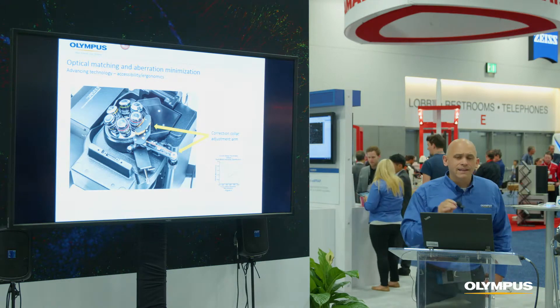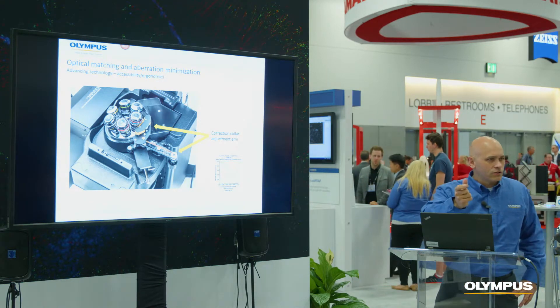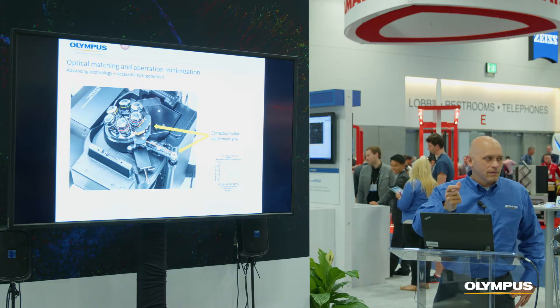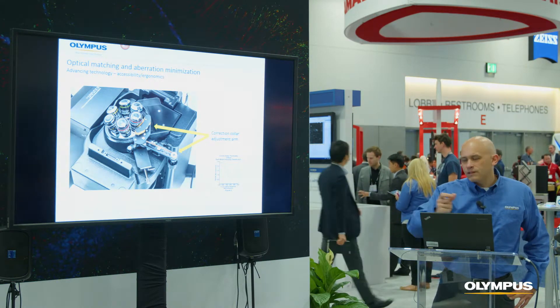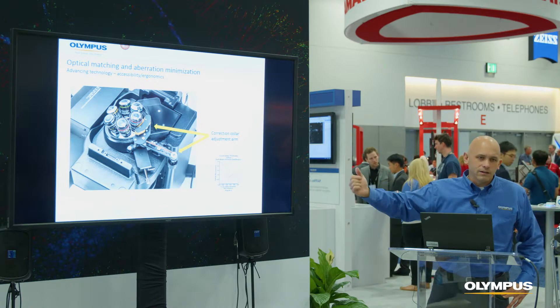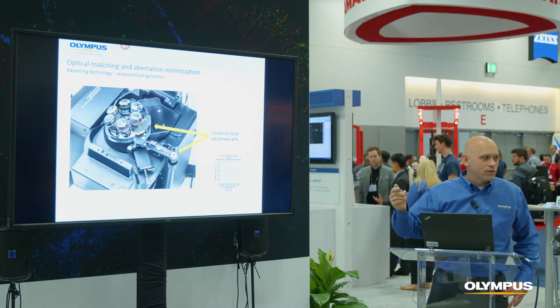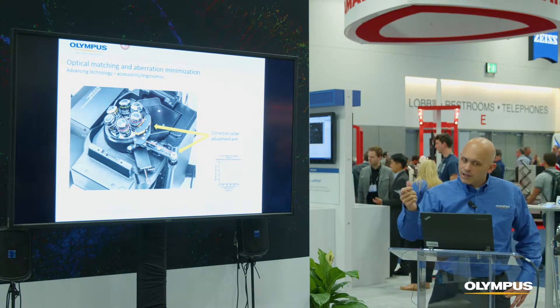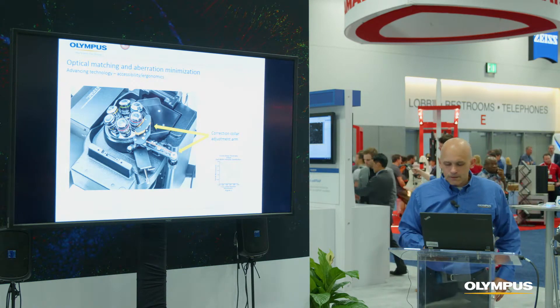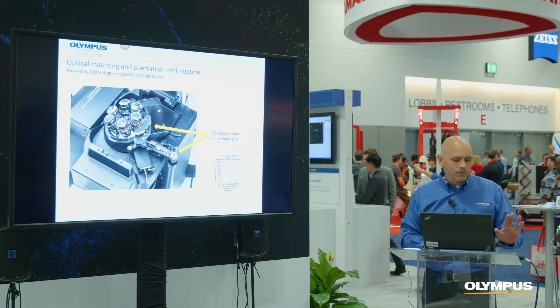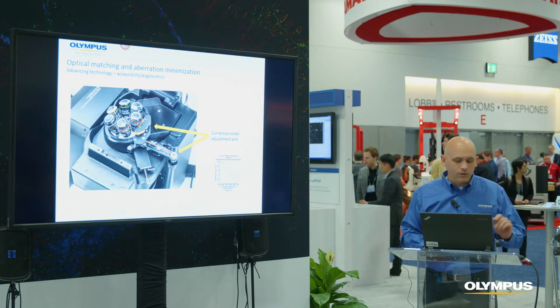Most people are not in the habit of reaching into their microscope and adjusting the correction collar — it's a completely new dynamic. But we facilitate this by creating a linkage external to the microscope that you can easily turn to adjust the correction collar. Now it becomes a simple way of manipulating that setting. You optimize that, and you optimize your signal — we should be doing it always.